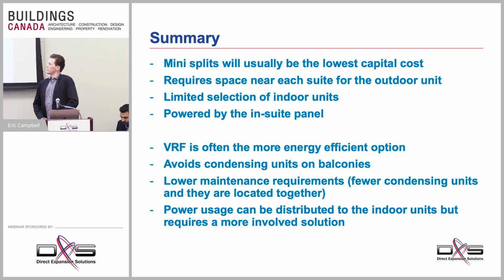Just a quick summary now in terms of the design considerations. Mini splits will usually be lowest capital cost, and there are very few situations where a VRF system will be less expensive to install than any sort of mini split system. We've talked about the limitations of mini split systems and why we do use VRF in a lot of these applications. We require space near the suite for the outdoor unit. Again, on the balcony or mounted right outside, there needs to be some local space for that condensing unit. There's a slightly limited selection of indoor units, not quite as many indoor units available with the mini split solution as there are with the VRF solution. Usually what is available is enough for most applications.